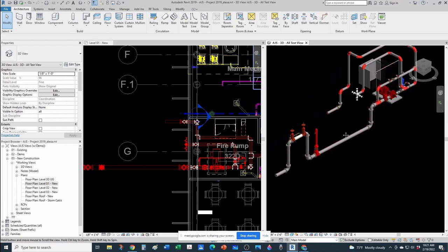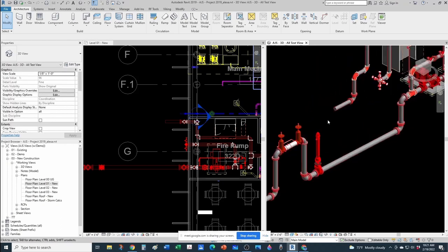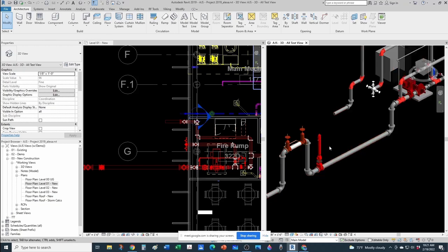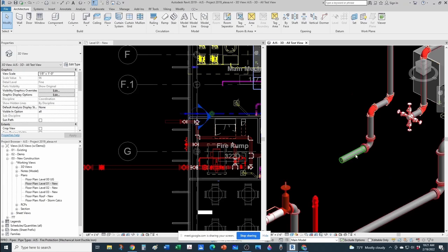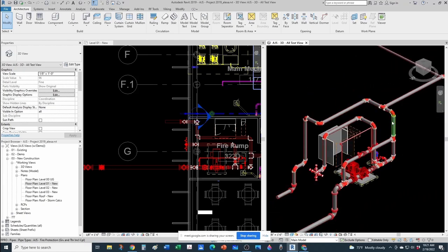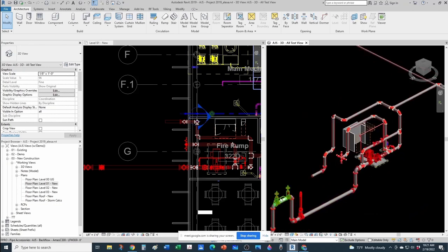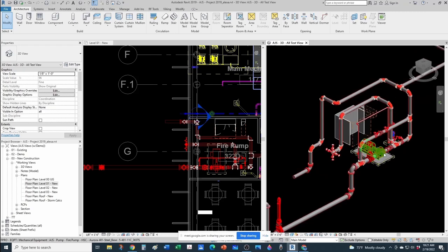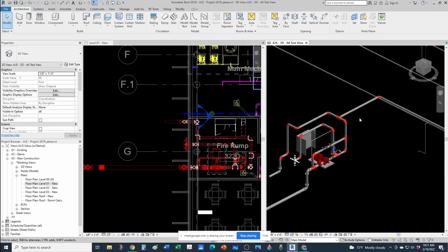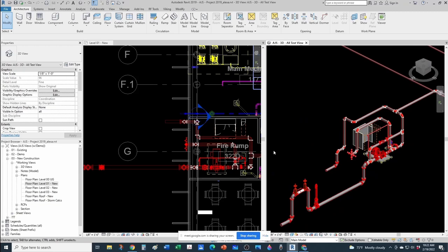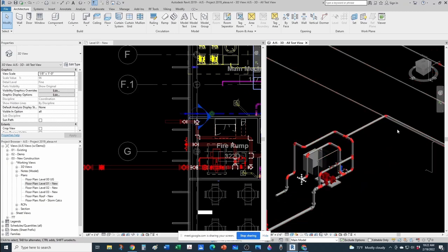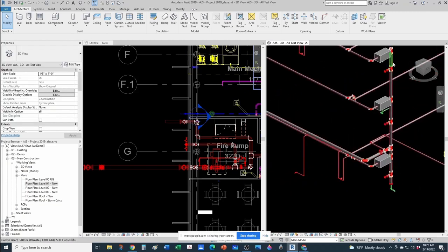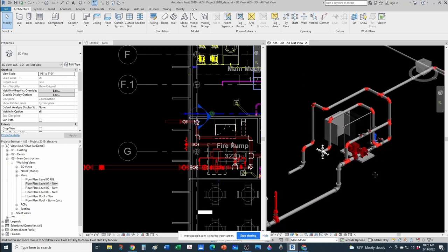So typically in those systems, even though you have a fire department connection close by, that line is a separate line, which in this case would be this one, that is connected at the outlet of the pump, so that you either pump from city pressure through your fire pump and into your system, or you have the already pressurized by the fire pump truck water going directly into your standpipe system. In this case, this would be my standpipe system.